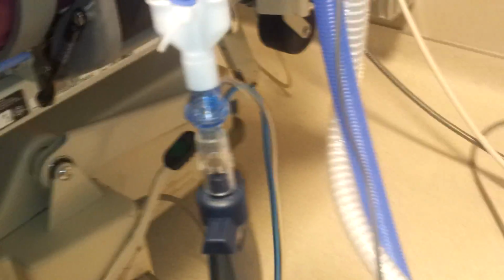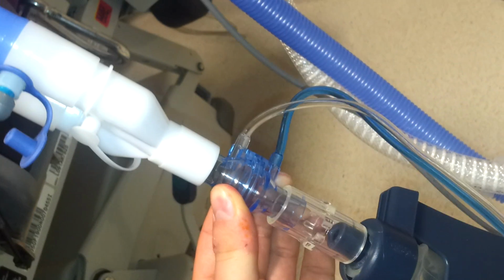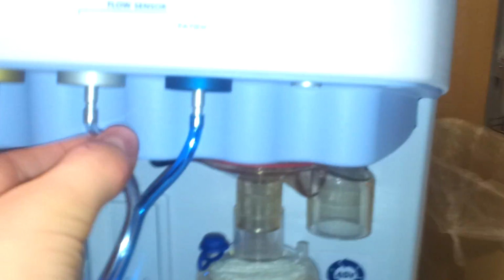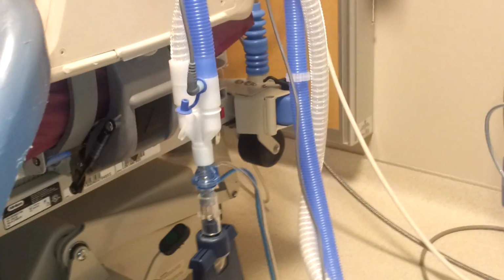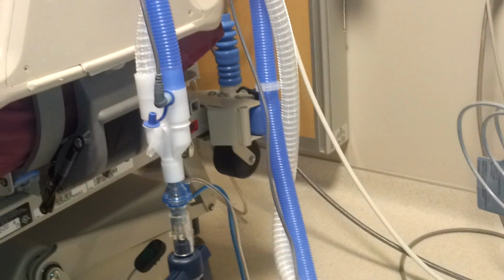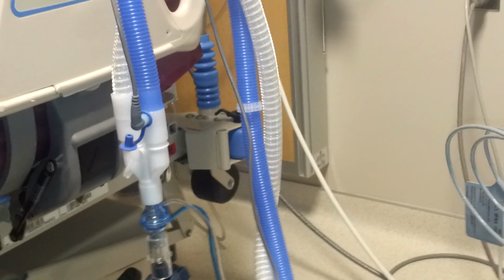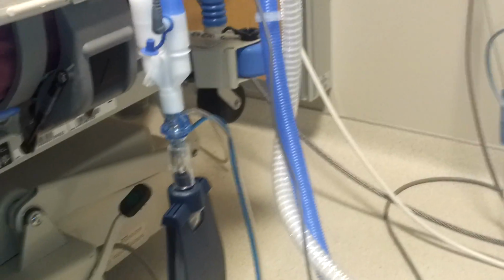Another main thing is the flow sensor is actually at the end of the patient circuit. So this little blue piece right there, and it hooks right here into the vent, so the flow sensor. Because the flow sensor is at the end of the patient circuit, when doing the pre-use check, the ventilator does not calculate tubing compliance. So yeah, that's a little bit different from the Servo I where the flow sensor is actually inside the vent.